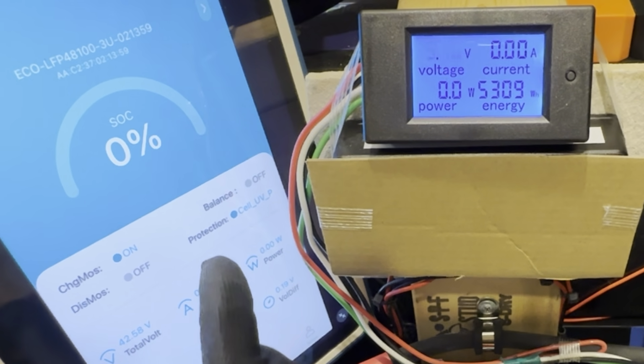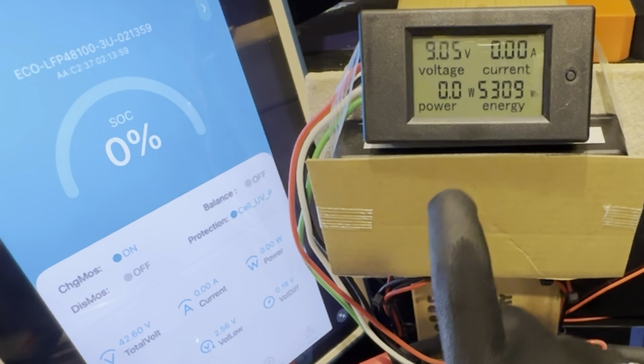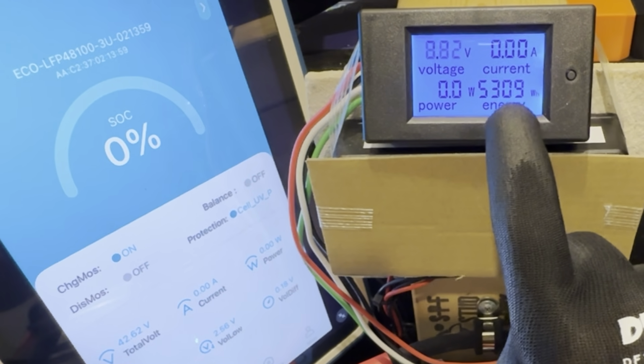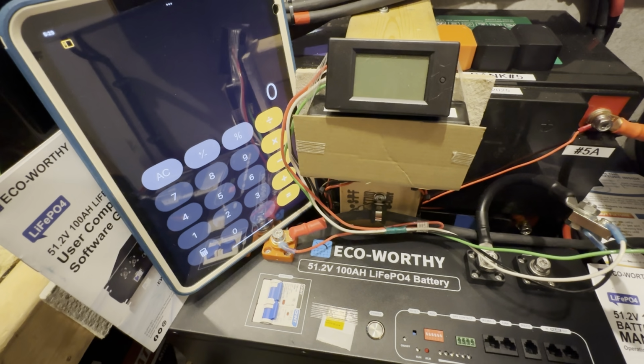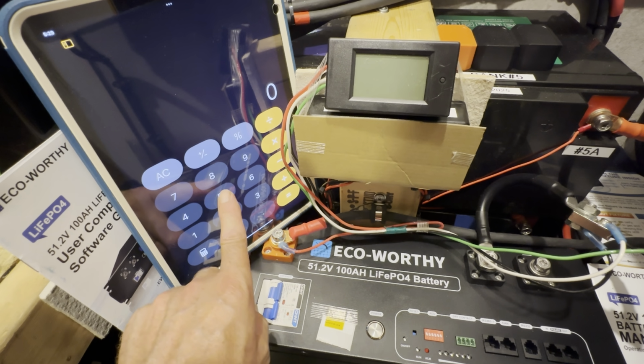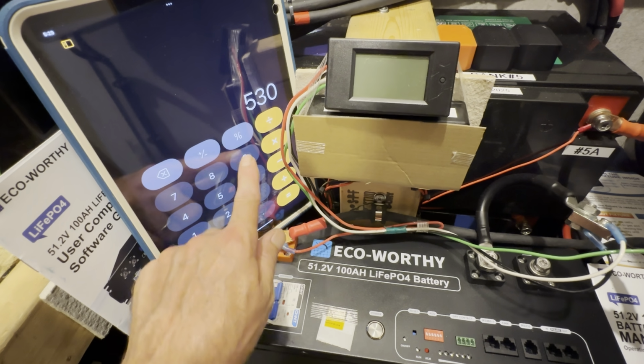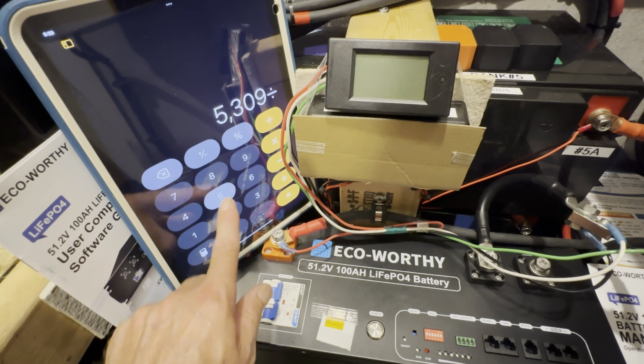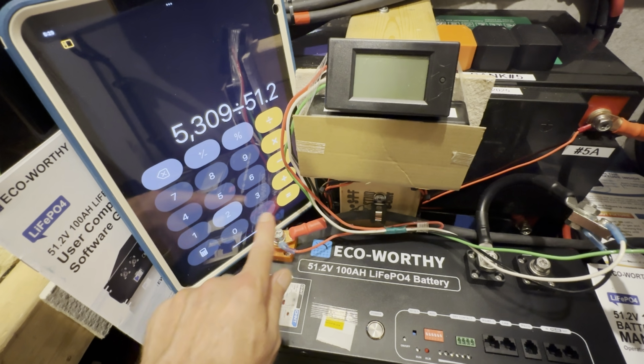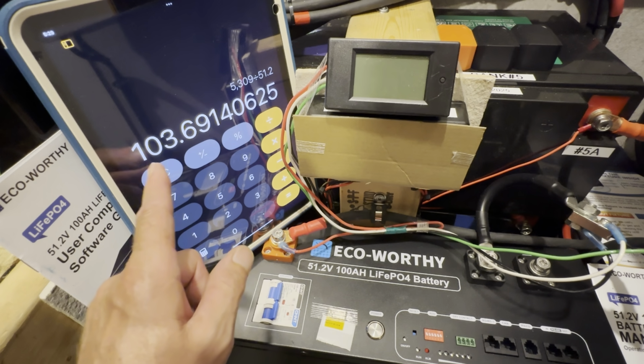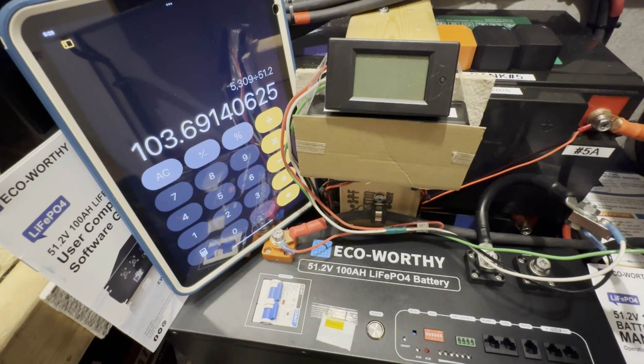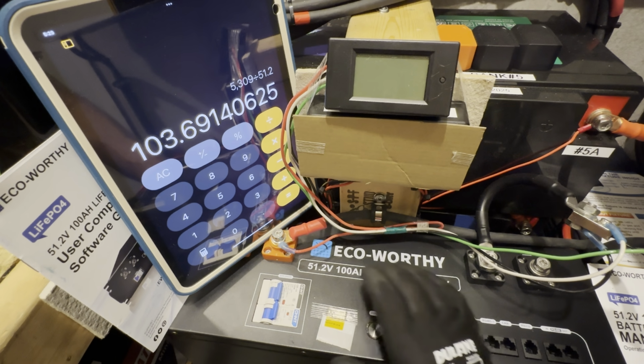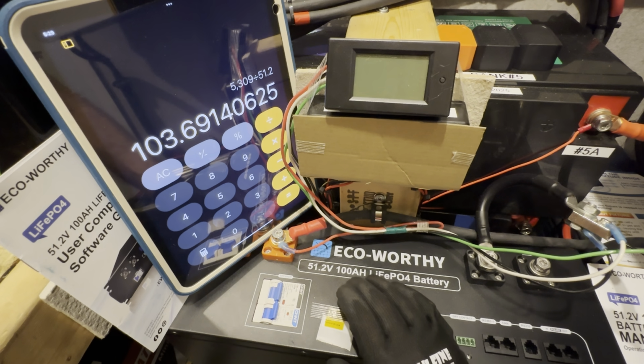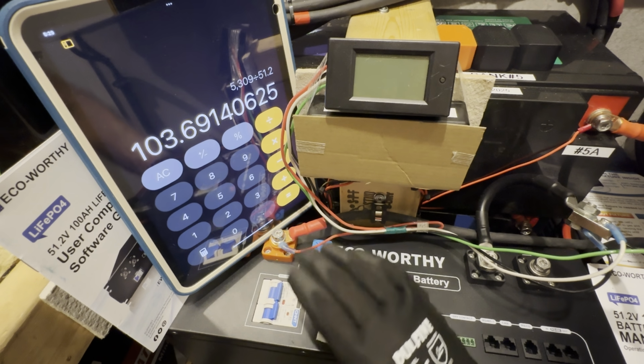So I ran the battery from cell over voltage to cell under voltage with a tally of 5,309 watt hours. So what's our final tally? We had 5,309 divided by a nominal 51.2 volts, so we had 103.69 amp hours out of the EcoWorthy. That's pretty good - that's kind of what I would expect out of brand new 100 amp hour cells, between 3 and 5% extra.